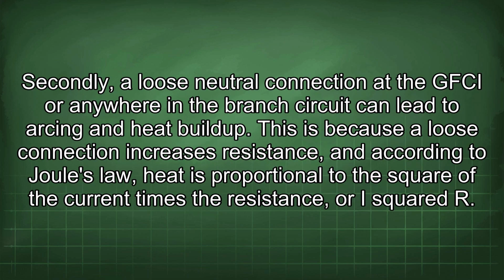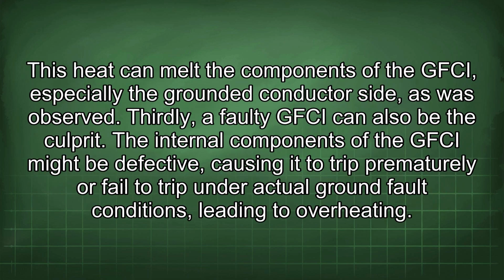Secondly, a loose neutral connection at the GFCI or anywhere in the branch circuit can lead to arcing and heat buildup. This is because a loose connection increases resistance, and according to Joule's law, heat is proportional to the square of the current times the resistance, or I squared R. This heat can melt the components of the GFCI, especially the grounded conductor side, as was observed.